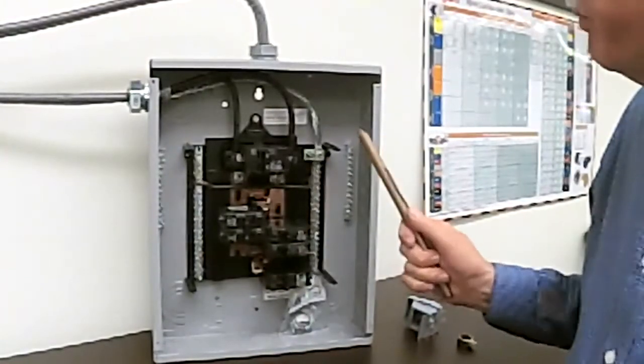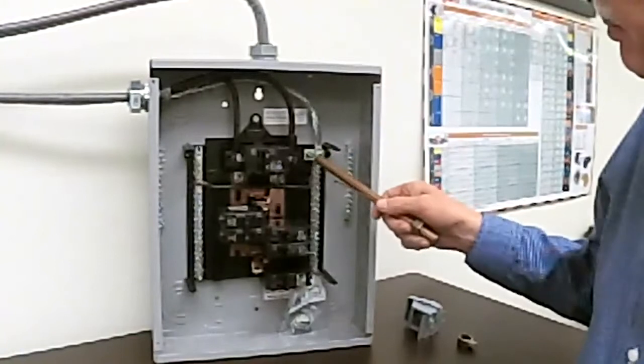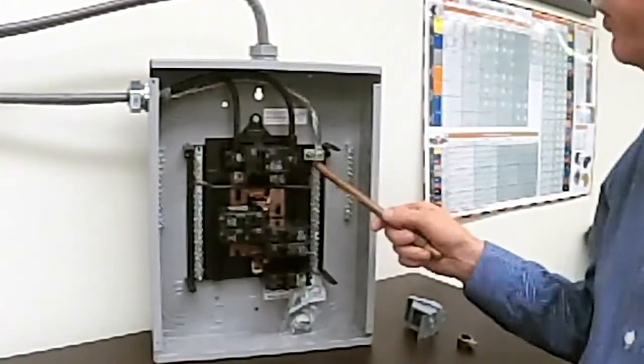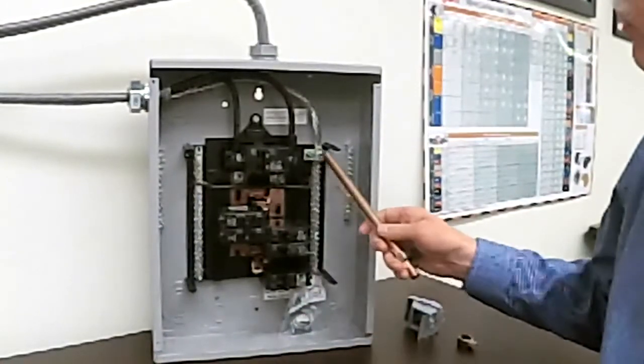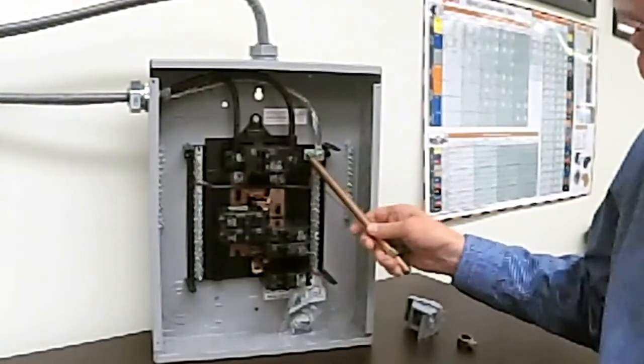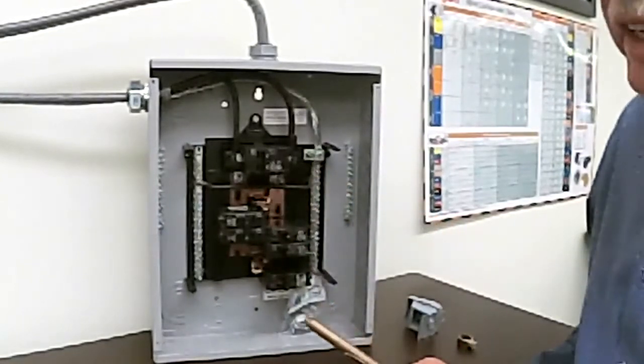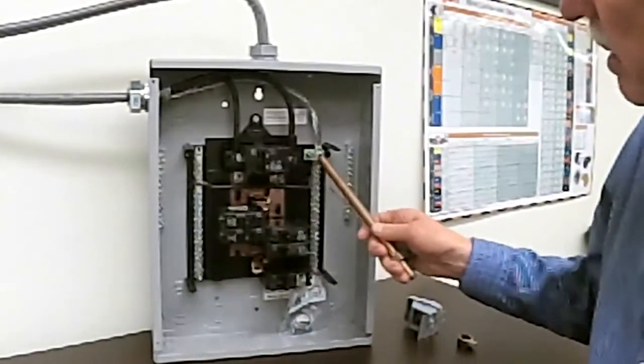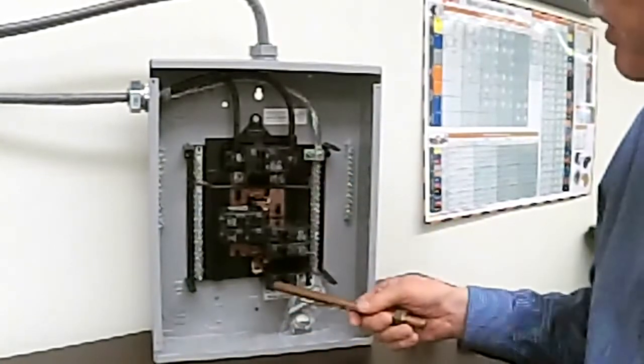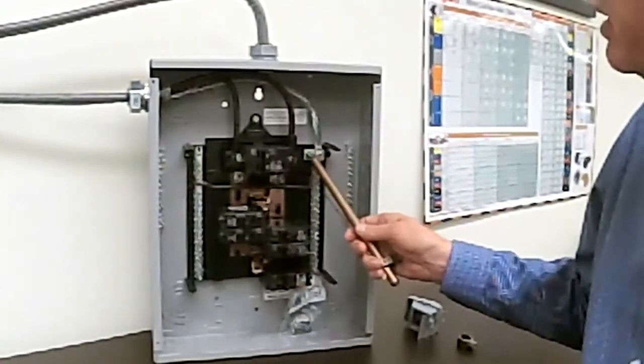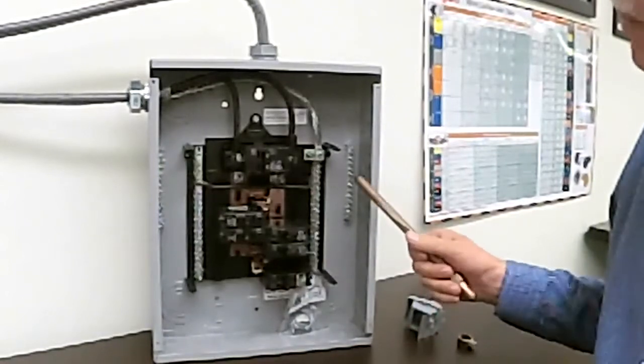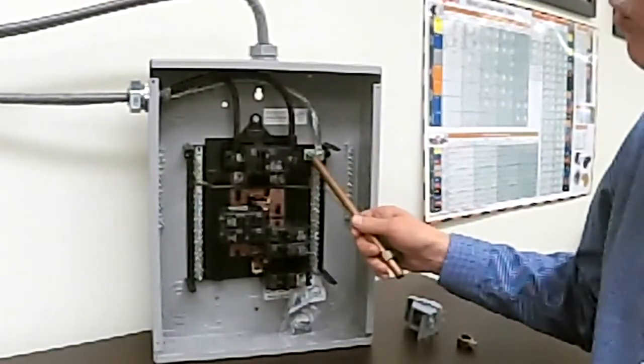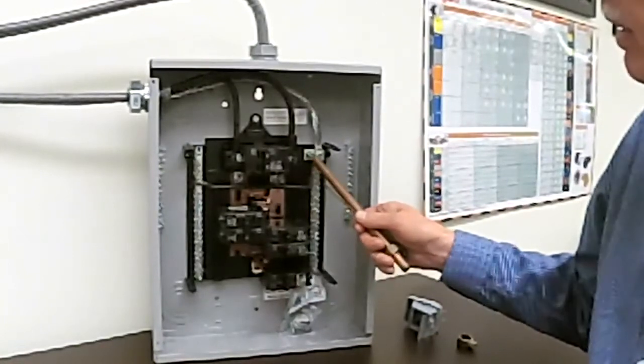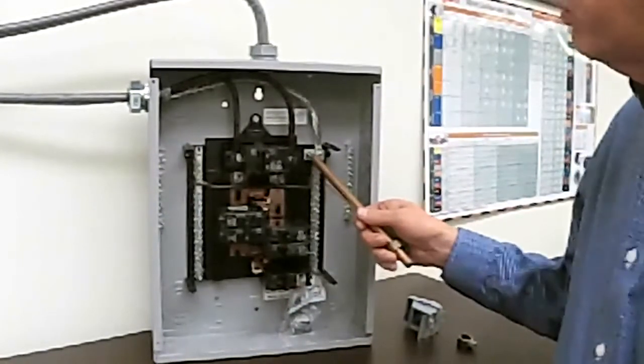The second thing here is the bonding screw. These are Siemens panels and they come with the bonding screw already installed. And this is the only screw in the whole National Electrical Code book that has to be green. The reason it's green is so the inspector can see it. Now, you might say, oh, they don't come in the bottom of the panel anymore. Well, some of them do, but Siemens does not. They come already in the hole, but they're not driven home. If this is a service panel, a main disconnect panel, you have to drive that screw home. And I mean drive it. It's not easy to drive that screw in.